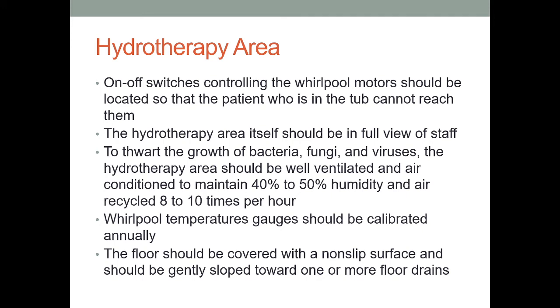Because of the amount of water associated with that, we have the potential for bacterial, fungal, and virus growth, and so ventilation and humidity become important components to monitor. You can see the recommendations listed there, as far as 40 to 50% humidity and air recycled 8 to 10 times per hour, and these are sorts of components that your HVAC people on your campus would be able to know and be able to monitor and provide changes if need be. All right, whirlpool temperature gauges need to be present and calibrated annually.